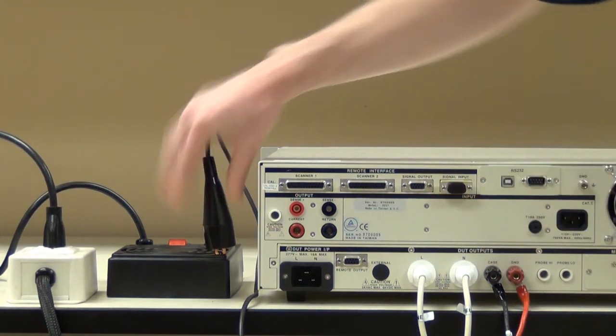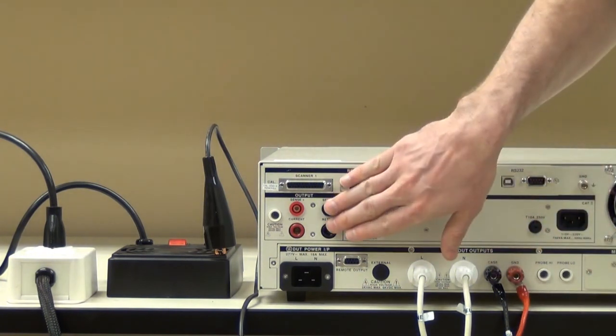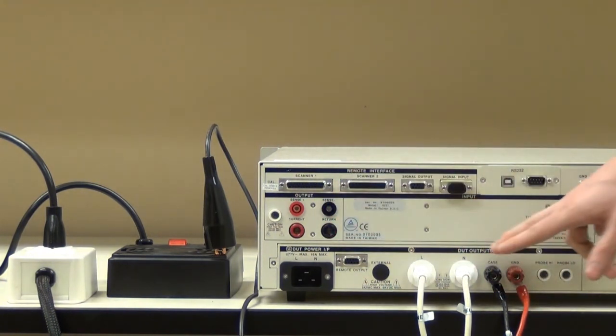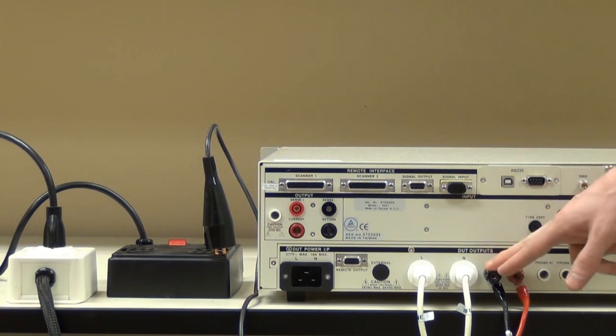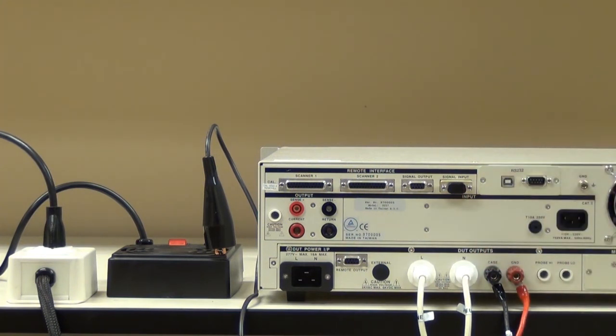The advantage of using case over the front and rear panel return is that when the functional run or line leakage test starts, there's a relay internal to case that opens, isolating the return circuit so that no damage can be caused.